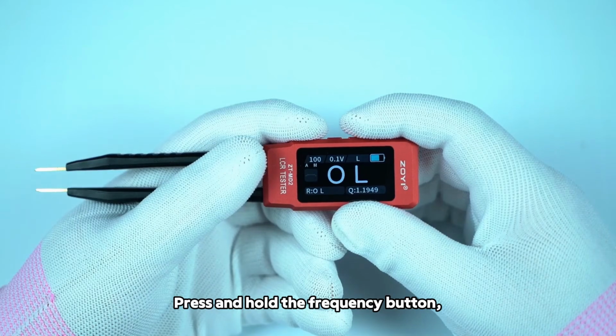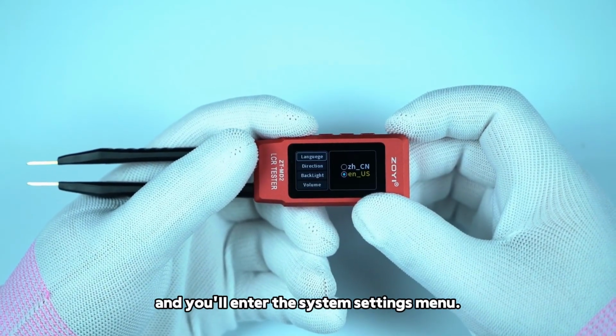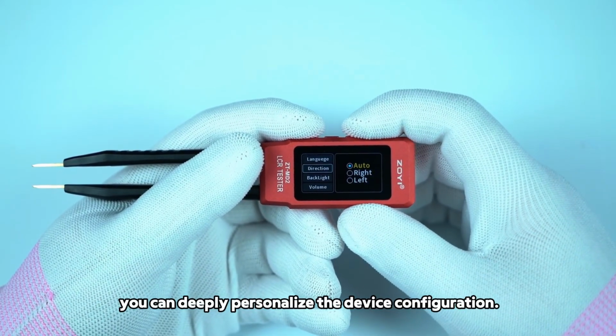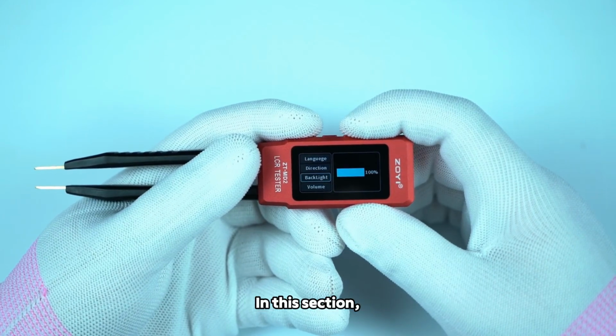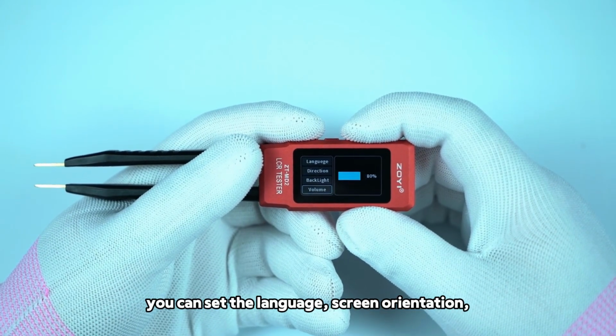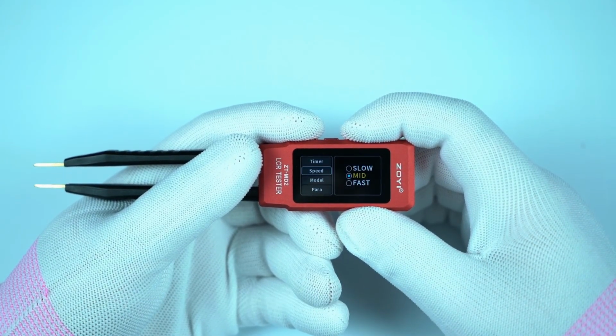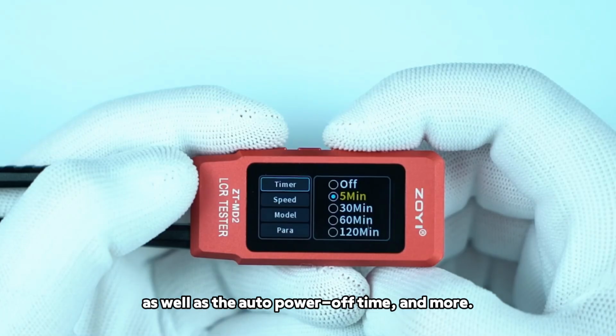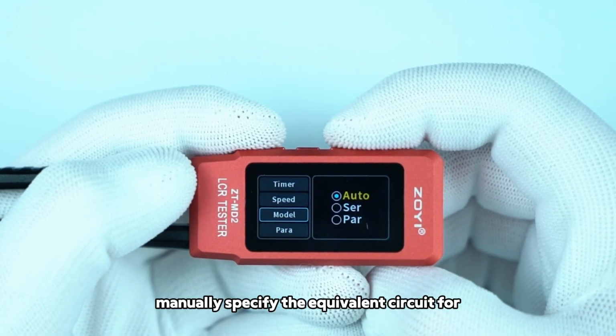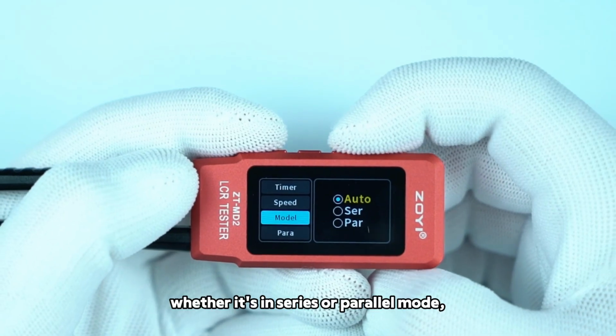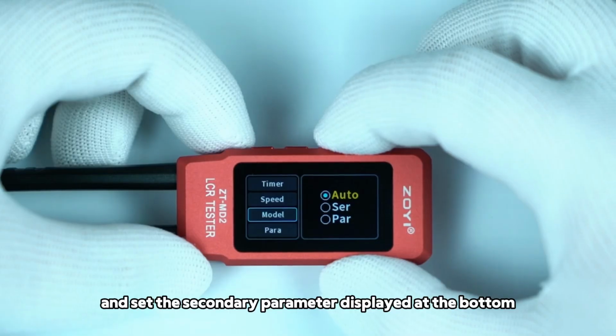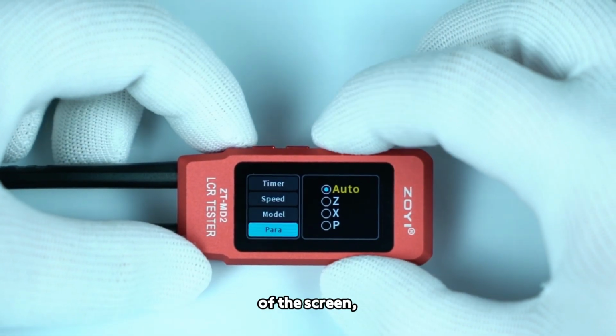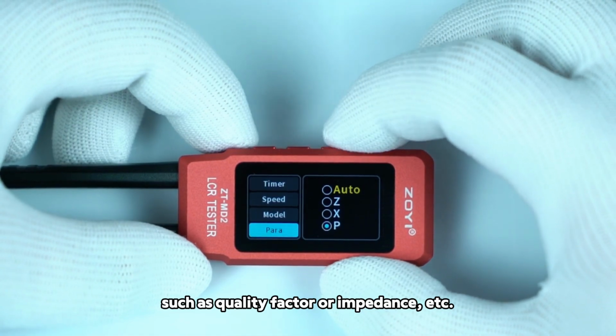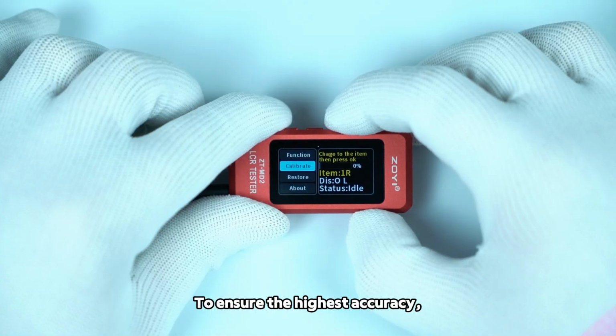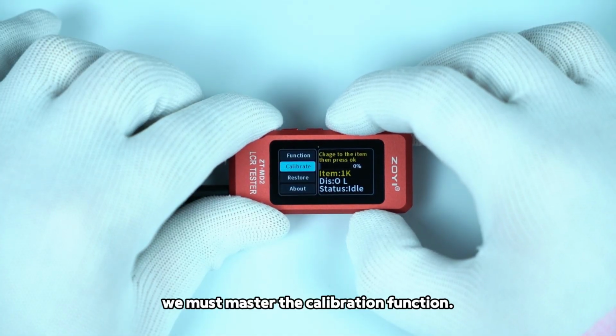Press and hold the frequency button, and you'll enter the system settings menu. Here, you can deeply personalize the device configuration. In this section, you can set the language, screen orientation, backlight, and volume, as well as the auto power off time, and more. You can also, as needed, manually specify the equivalent circuit for measurement, whether it's in series or parallel mode, and set the secondary parameter displayed at the bottom of the screen, such as quality factor or impedance, etc. To ensure the highest accuracy, we must master the calibration function.